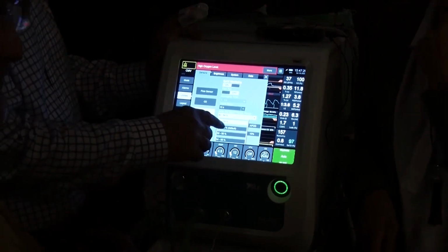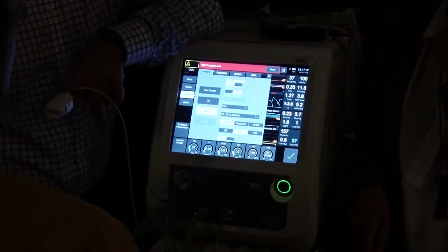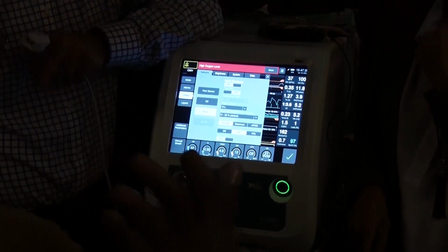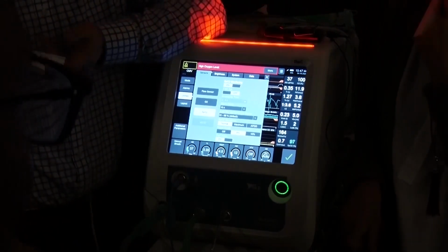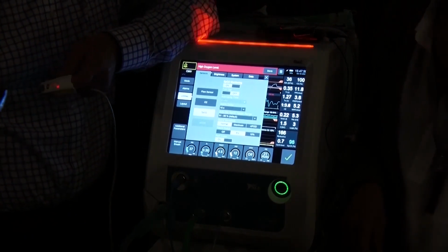The lowest one is, I clicked that one. So we have a cyanotic baby? No, you cannot do that. It cannot be used for cyanotic babies. Yeah, and that's important. It's not stable, but it could be upgraded in the next software, because then you can have something like 60 to 80 as a range. The dissociation curve is different. It's very different, so you have to rewrite it, to write a new piece of software.